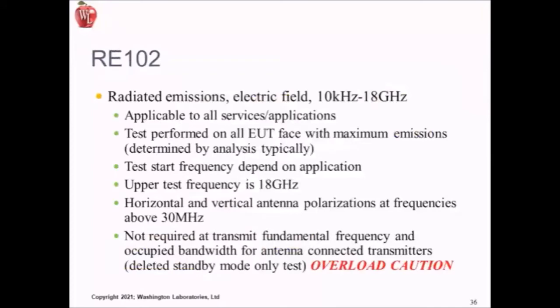Getting to the radiated emissions test, RE102. This is applicable across the board pretty much. 10 kilohertz to 18 gigs is the specified frequency range. Pretty much every type of device that goes through the MIL procurement spec gets this testing done. And the whole idea is to minimize the amount of electric field emanating from cables and cases, and this is to minimize the interference to other radio services. We have to do horizontal and vertical polarities. You may have to do multiple faces. Again, this would be called out by the test plan. Again, a little bit of tailoring here.